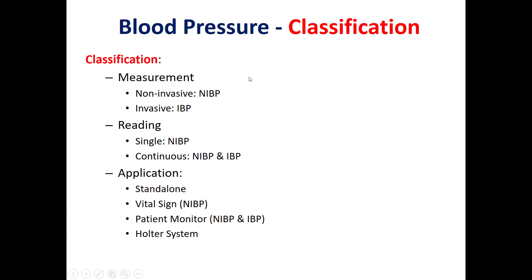Blood pressure instrumentation classification. Blood pressure instrumentation can be classified in different ways. The first way, which will be adopted in this lecture, is based on the measurement: invasive or non-invasive. It can also be classified based on whether it provides a single reading or a continuous reading. In its application, it can be a standalone blood pressure device or part of a device measuring many other parameters.